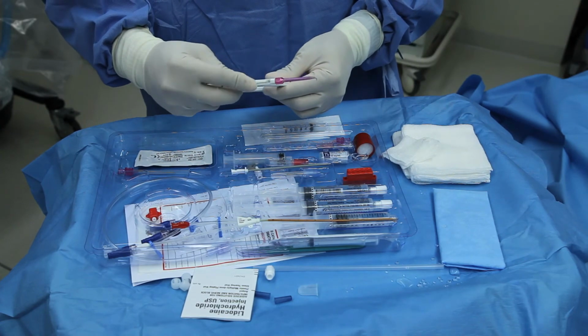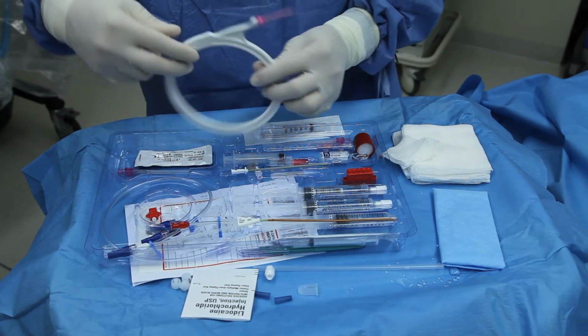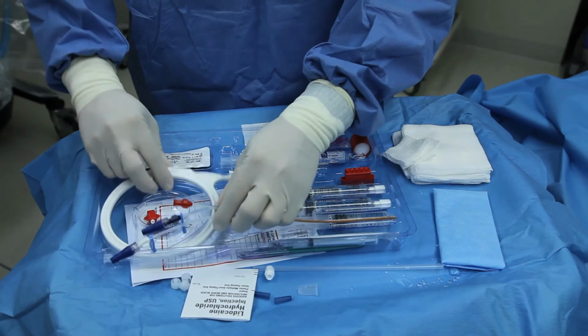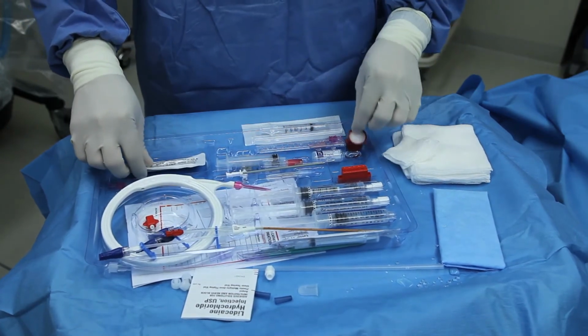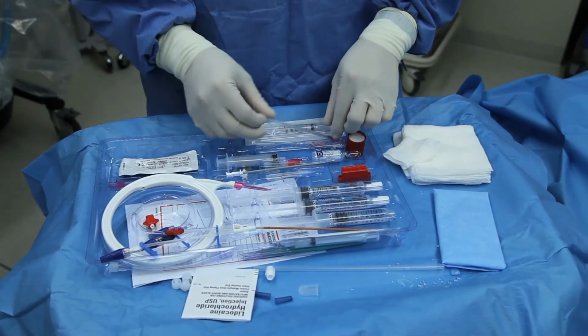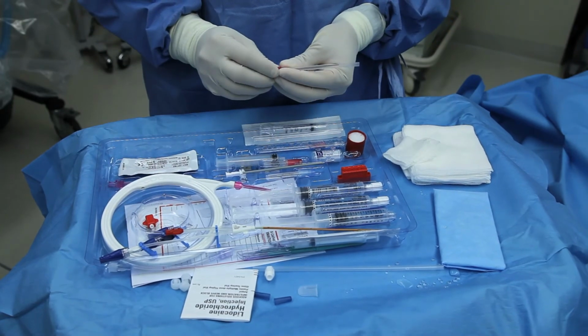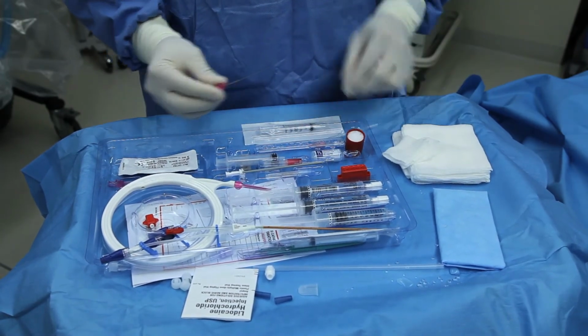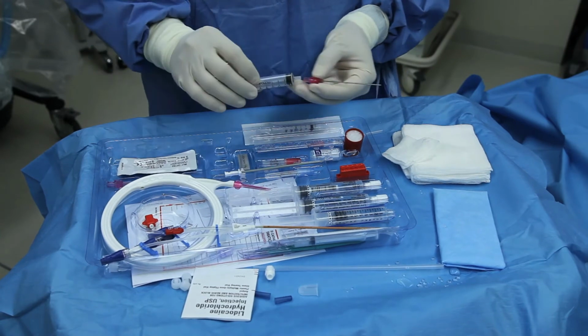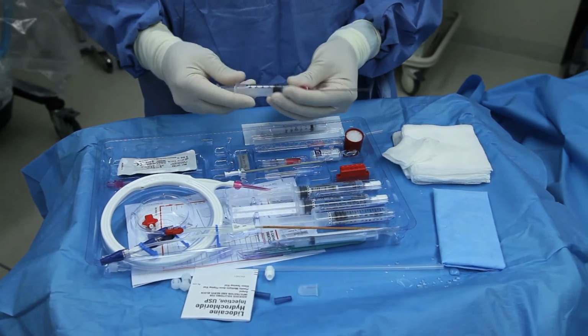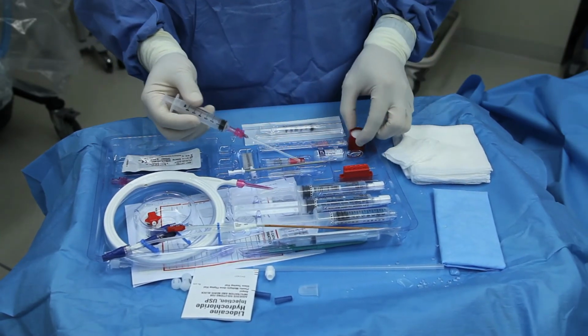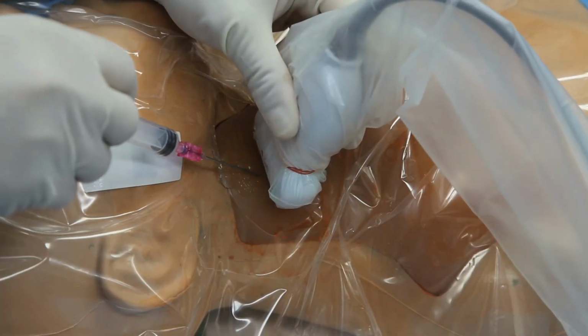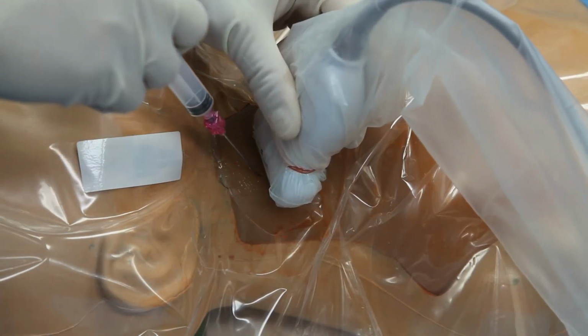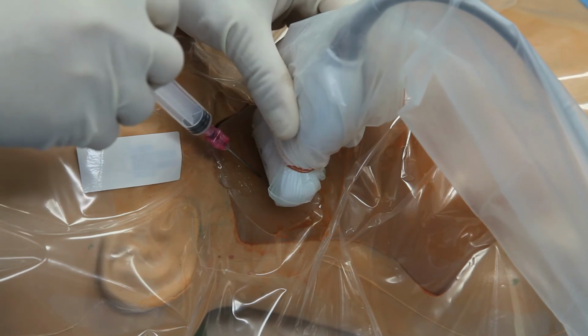Prepare the guide wire by removing the protective cap from the end of the wire housing. You'll notice the end of the wire is flexible and looped into a J. This should be pulled back into the housing before you begin. Locate the introducer needle and remove its protective cover, then place the needle on the non-threaded syringe. If you haven't done so already, place the patient in a slight Trendelenburg position to dilate the target vessels.